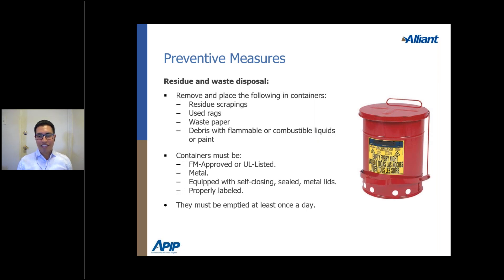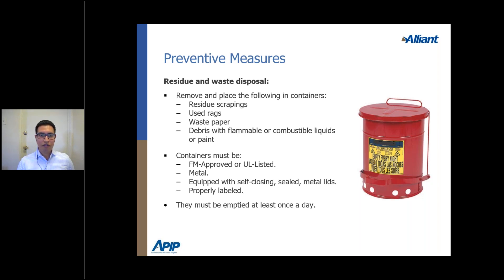Oily waste cans should be emptied at the end of each shift. The reason for disposing oily rags and materials in these special containers is spontaneous combustion. If oily rags are disposed of in a regular trash can, there's a hazard of spontaneous combustion occurring. These specialized containers keep any spontaneous combustion confined within the oily waste can.